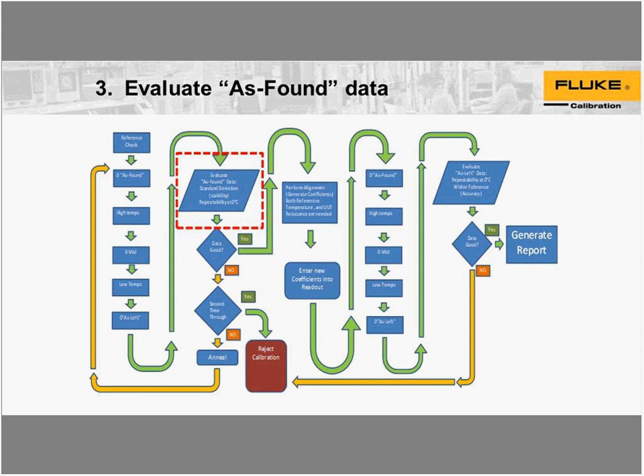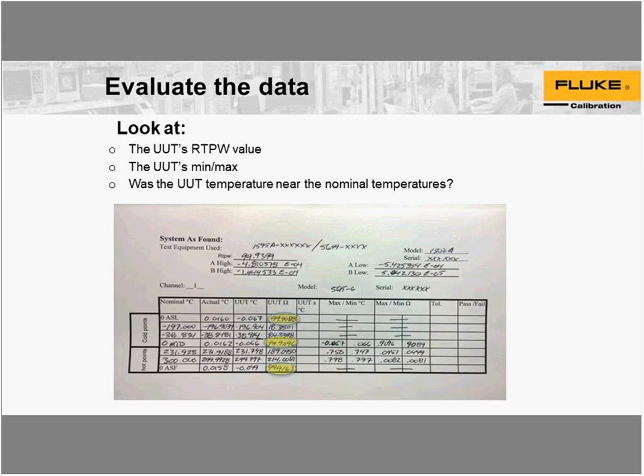And there are certain criteria that you want to look at. Right. You want to look again at the RTPW values. You want to make sure they're following very close. You also are looking at the other temperature differences. If they're not bad, that's great. The concern is you want to have a stable RTPW that says, okay, our probe is very repeatable and we get some good measurements out of it.